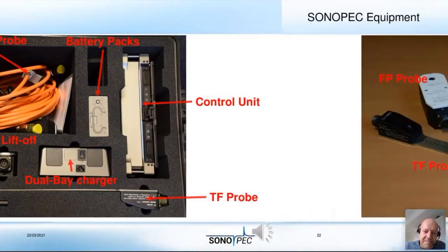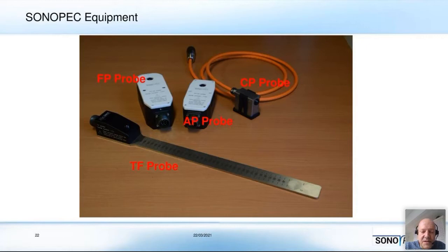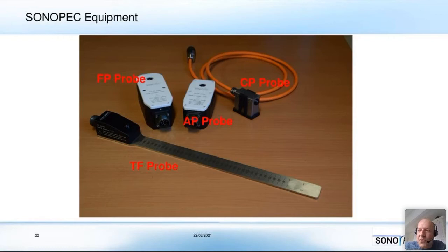We have mainly four probes. The tank floor probe is coded as TF probe. The FP probe is the stronger probe, going up to 200–250 millimeters insulation, with wall thickness up to 70 millimeters. The AP probe has a smaller application range — insulation up to 75–80 millimeters and wall thickness up to 30 millimeters. The contact probe and tank floor probe have wall thickness and standoff up to one inch, or 25 millimeters. For example, a pipe with thick bitumen coatings can be easily inspected with the contact probe.